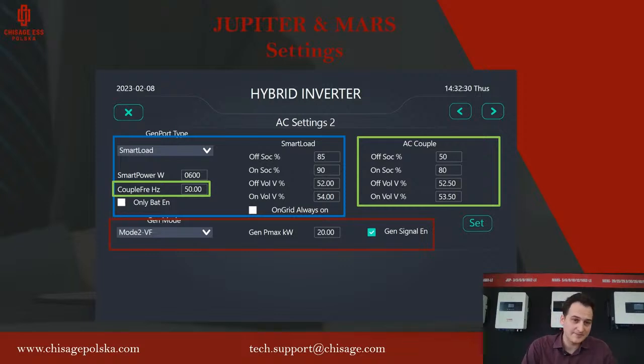For the gen mode, we have mode 1 and 2. Basically, mode 2 is more used in genset when the power of the genset is lower than the inverter power, and if it's higher than the inverter power, we have to use mode 1. But you have to check this on site. So if mode 2 is not working, try mode 1. It depends on the genset which we use. So check mode 1 and mode 2. One of these should work.